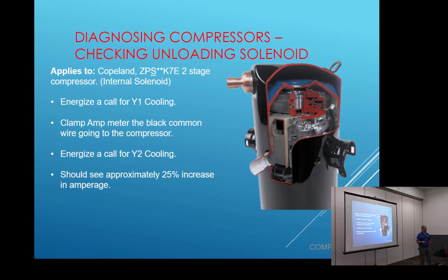Let's put our gauges on it, put our amp meter on our compressor. So if we're calling for Y2 already, and we pull that 24-volt wire going off to that solenoid, we should see a 25% decrease in amperage and pressure drop. If we don't, we probably have a solenoid in a compressor that's not working. If we plug it back in and you don't see any amp change or pressure change, you have a bad solenoid inside that compressor. So if it's the Copeland, what do you have to do to fix it? Hold on a second, though. But just because it didn't, could our rectifier be bad going into the side of that compressor?